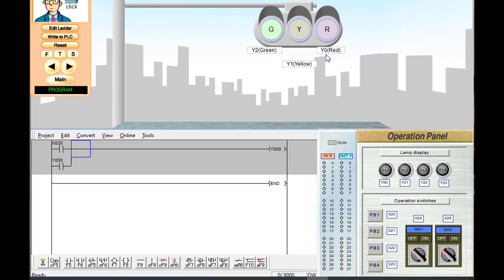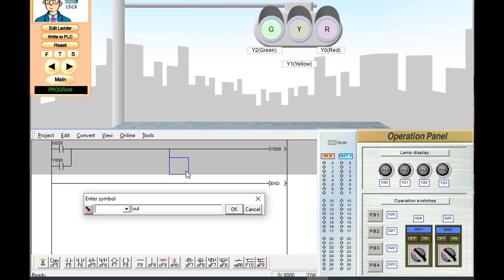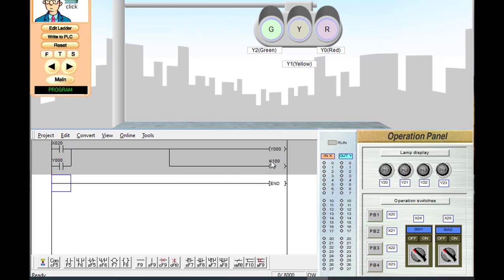Now this red light has to be on for 10 seconds, so we start a timer for 10 seconds. We take a vertical line and write timer T0 with preset time K100 — because the time base in Mitsubishi PLC is 100 milliseconds, so K100 equals 10 seconds. When the start button is pressed, Y0 will be on and timer T0 will start. After 10 seconds, T0 comes on, and we write NC of T0 to unlatch Y0, turning off the red light.